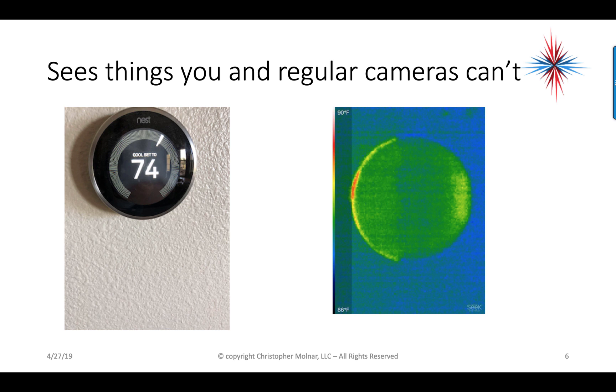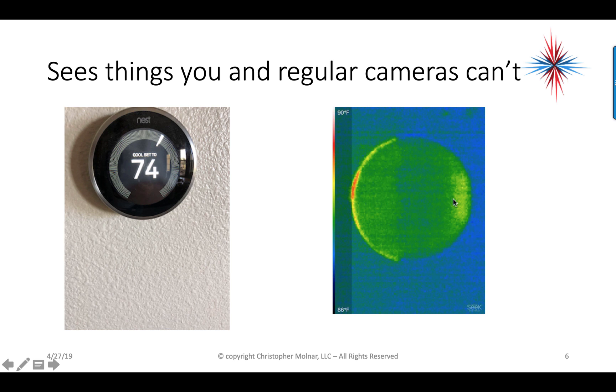What the infrared is doing is it sees things that a regular camera can't. For example, the picture on the left is a Nest thermostat. On the right, it's showing you the heat signature put off by the Nest thermostat. There's a little bit of heat coming off this side because this thermostat has a digital display, and heat is generated anytime power is being used. The rest of it is a little bit warmer than the surrounding wall, which is the cooler blue color. When looking at colors, cool is blue, and as you go up on the color scale it goes into reds and whites. The color scale is shown on the left of the picture.